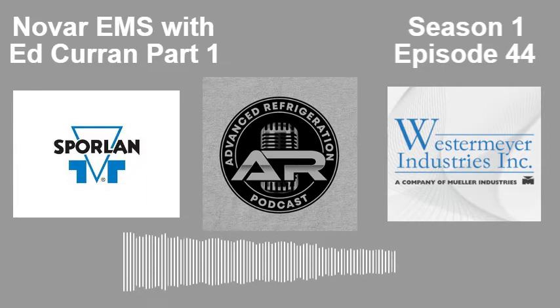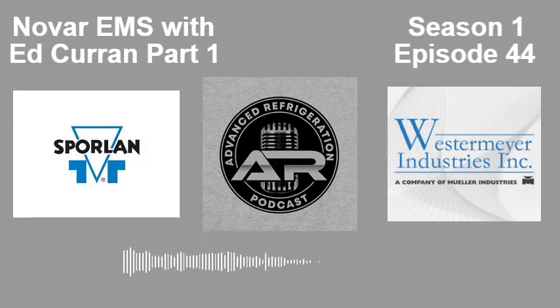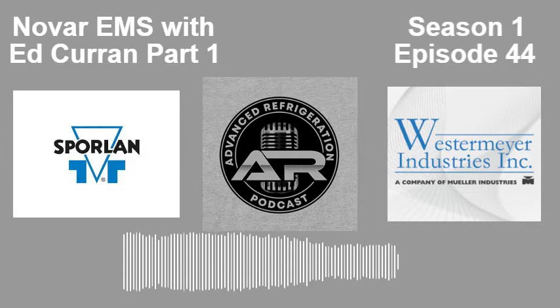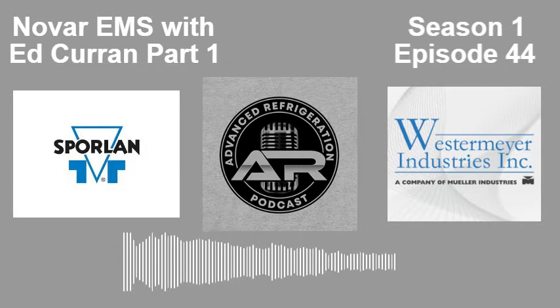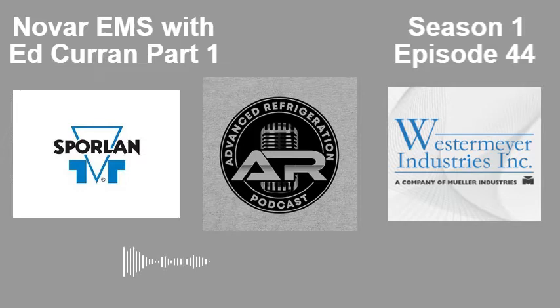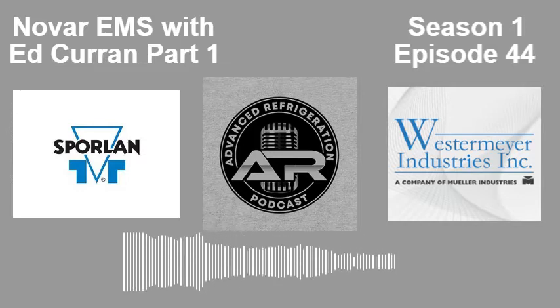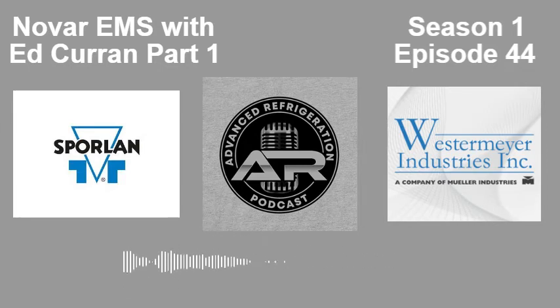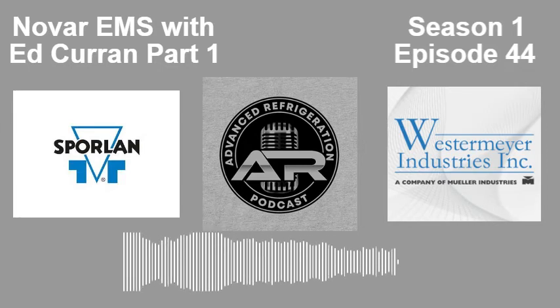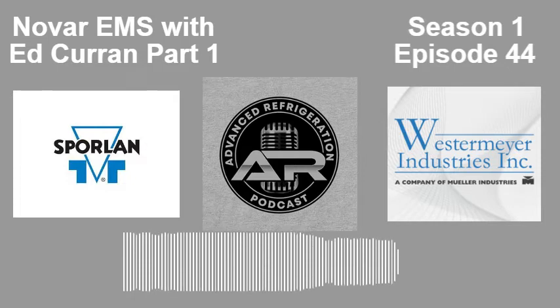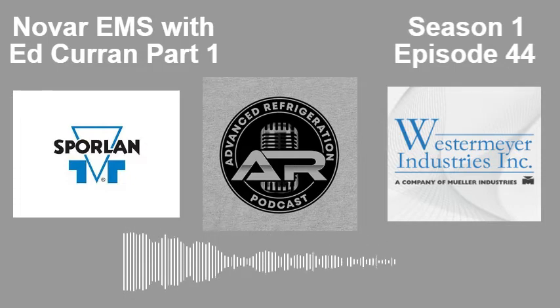Something else people should know is on these legacy boards, there's two ways to address them - they're either going to be addressed with dip switches, or addressed via jumpers. It's important to know that on those dip switches, and this is something we continue today, we don't address on, we address off. It's a binary addressing, but it's in the off position, so it always throws everybody off. We are consistently keeping that - not my decision, but it is what it is.